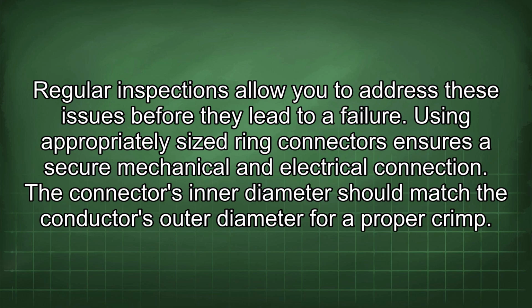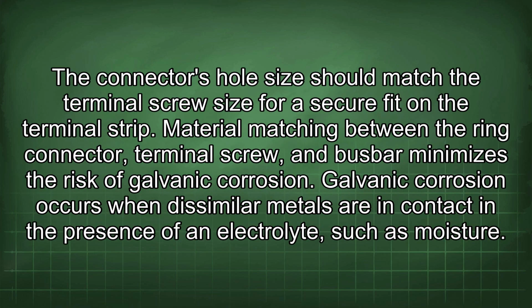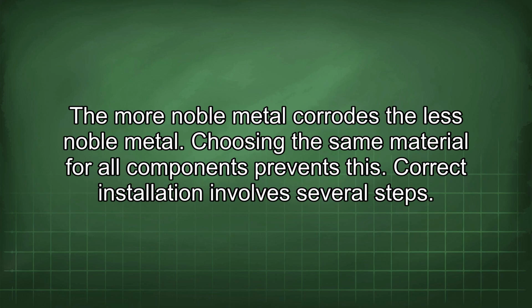Using appropriately sized ring connectors ensures a secure mechanical and electrical connection. The connector's inner diameter should match the conductor's outer diameter for a proper crimp. The connector's hole size should match the terminal screw size for a secure fit on the terminal strip. Material matching between the ring connector, terminal screw, and busbar minimizes the risk of galvanic corrosion. Galvanic corrosion occurs when dissimilar metals are in contact in the presence of an electrolyte, such as moisture. The less noble metal corrodes, not the more noble metal. Choosing the same material for all components prevents this.